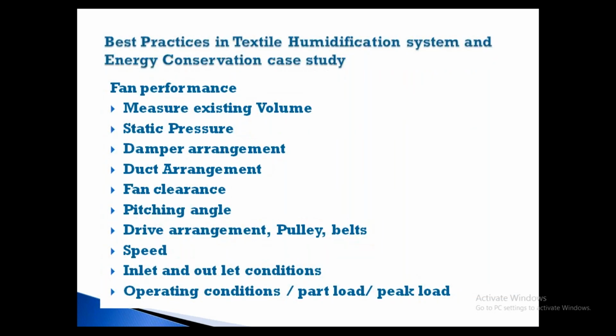So if you are going to study the performance of your humidification system, when you want to see the fan, as with centrifugal fans, you open the fan and see what type of impeller it is, whether it's a backward curve, which curve. Like that, you have to take the reading, measure the existing volume, and see the fan clearance. This is very important. As he also mentioned, the fan clearance between the fan casing and impeller is very important. The lesser the clearance, the more efficient the fan.